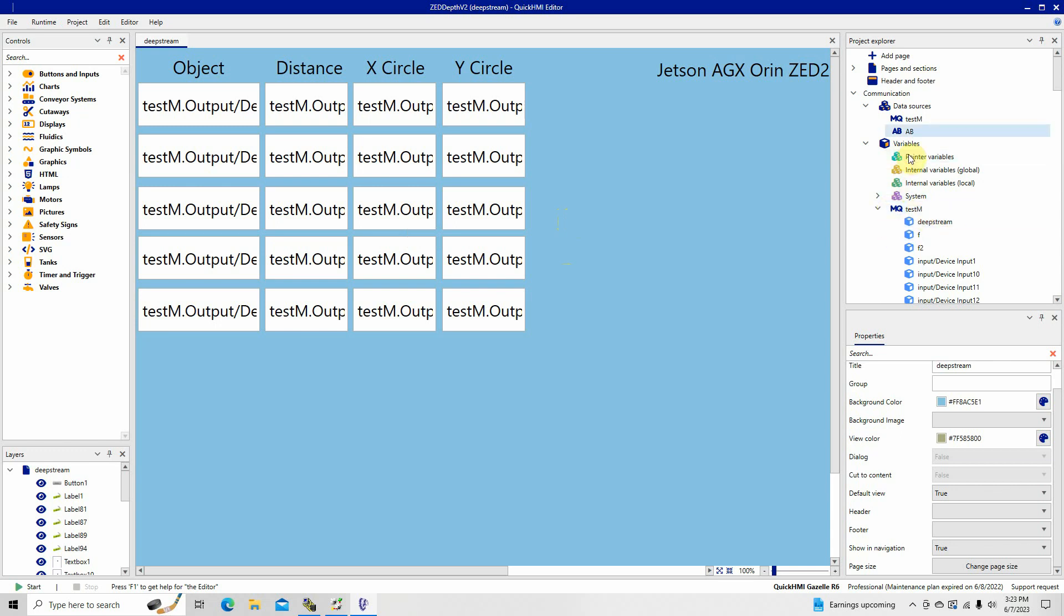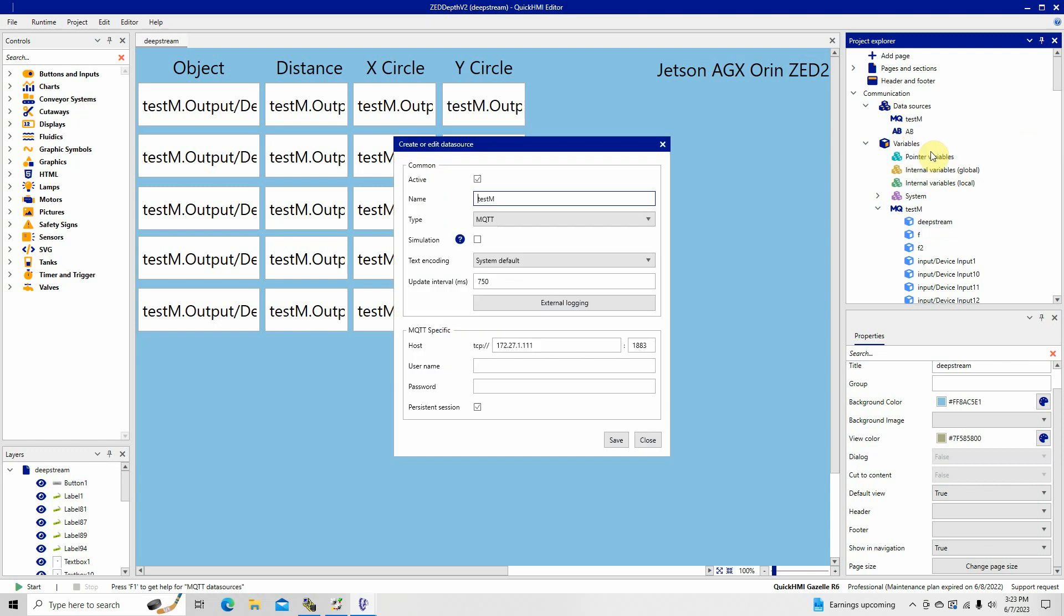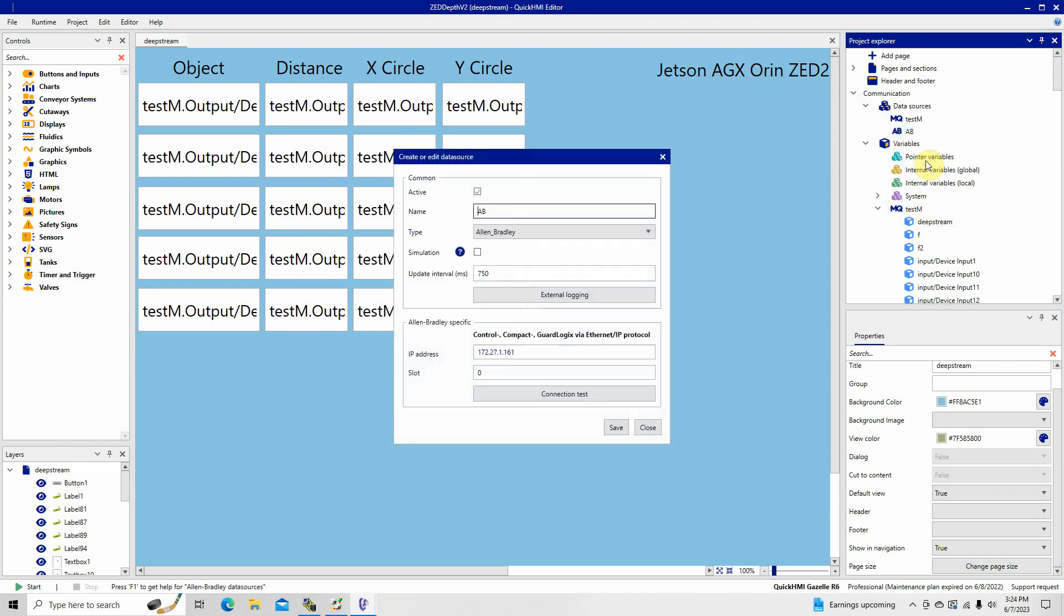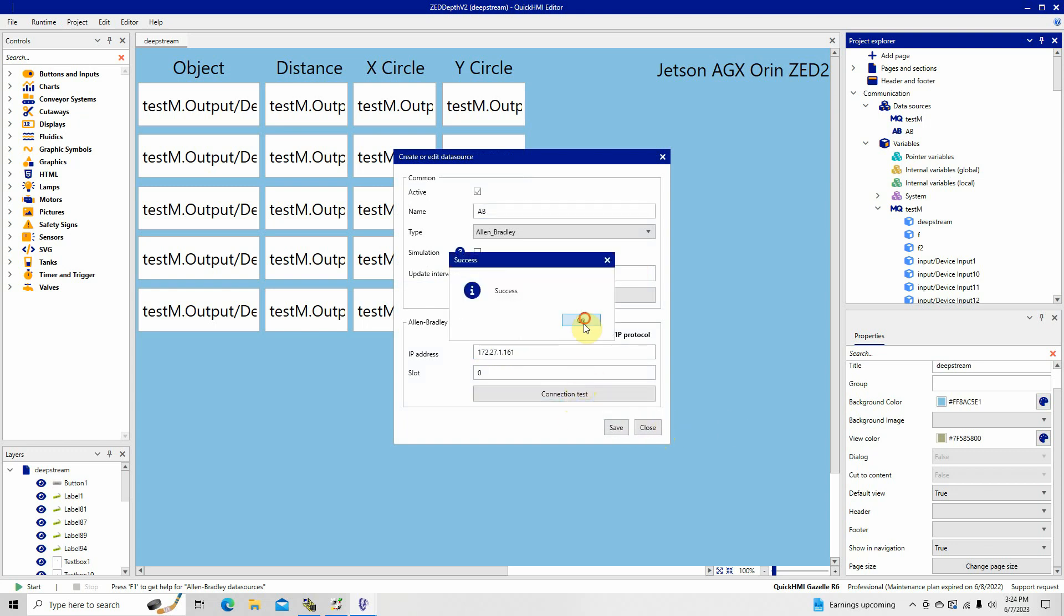At the same time, it sends it right back out to the PLC. Right here, these are my two data sources. It's the MQTT server. That's the address of the AGX Orin. That's important. You got to have that or I won't know where to target. Then right here, this is the Allen Bradley, and this is the IP address of my Control Logix processor right there. Do a connection test. It says that it's good. That's where I'm collecting the data.